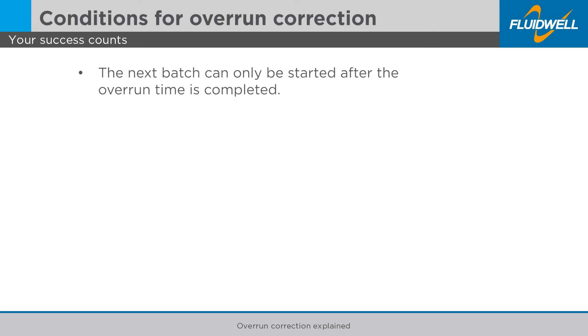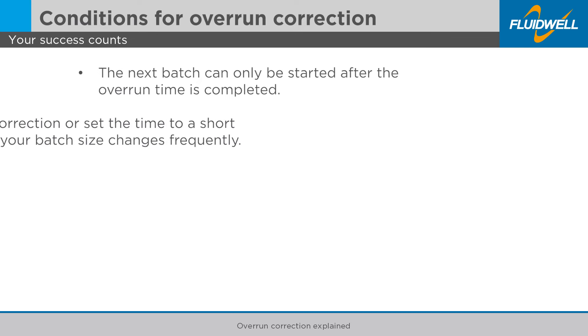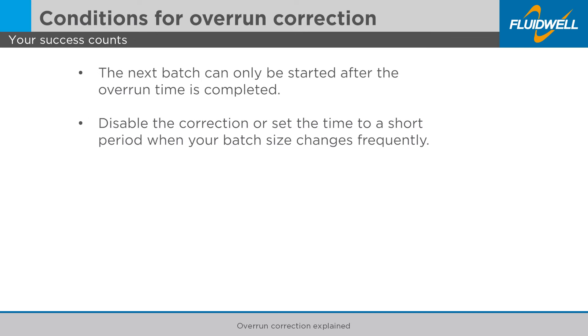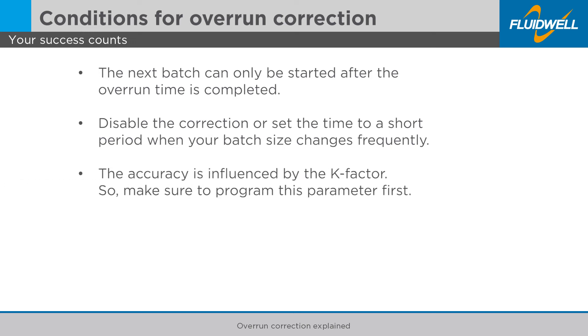Conditions for optimal overrun correction: The next batch can only be started after the overrun time is completed. Disable the correction or set the time to a short period when your batch size changes frequently. The accuracy is influenced by the k-factor, so make sure to program this parameter first.